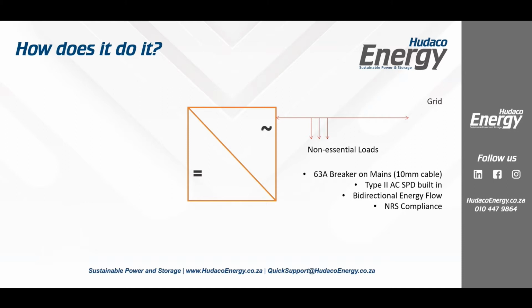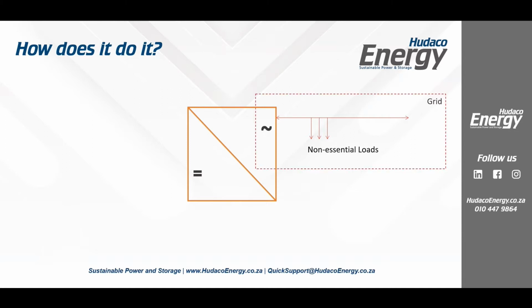It's got type 2 surge protection built in, and we can import energy and export energy through this port. It's a bidirectional energy flow, and this is really important for the rest of the discussions this morning. It's also NRS compliant, so we've got the certificates in place, and it is on the City of Cape Town's list. So that's the grid port.